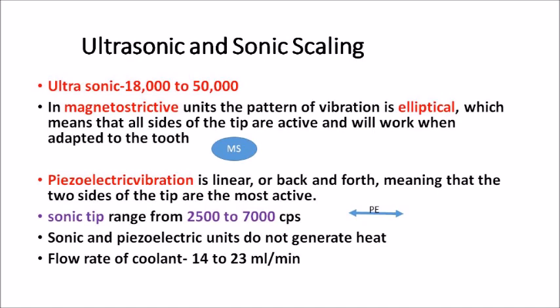Look at that arrow mark. So it is just moving back and forth. This means only the 2 sides of the tip will be most active. For magnetostrictive, it is elliptical, so all around that area it is active. Here it is back and forth and only the 2 ends are active. Magnetostrictive is elliptical, piezoelectric is back and forth or linear.